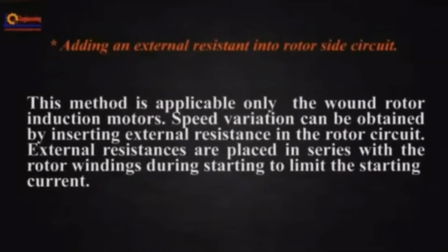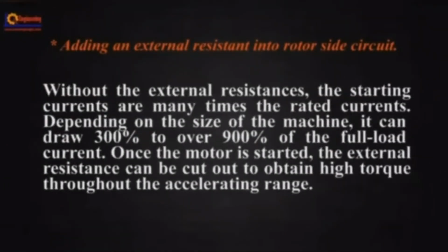This method is applicable only to wound rotor induction motors. Speed variation can be obtained by inserting external resistance in the rotor circuit. External resistances are placed in series with the rotor winding during starting to limit the starting current. Without the external resistance, the starting currents are many times the rated currents, depending on the size of the machine. It can be 300% to over 900% of the full load current. Once the motor is started, the external resistance can be cut out to obtain high torque throughout the accelerating range.